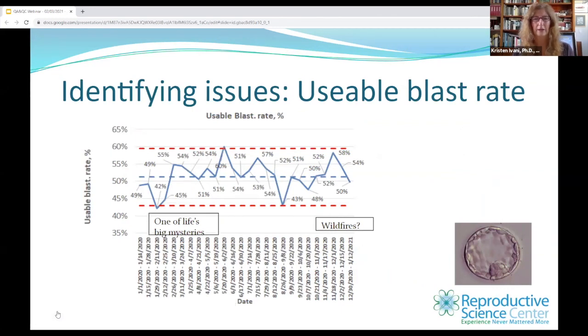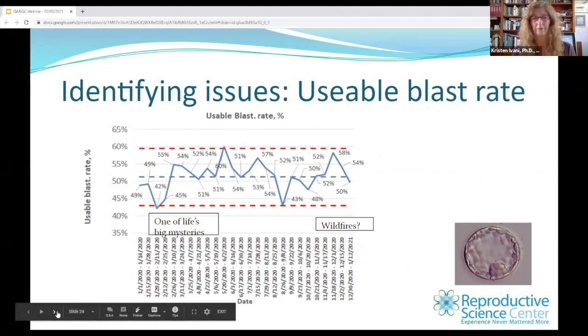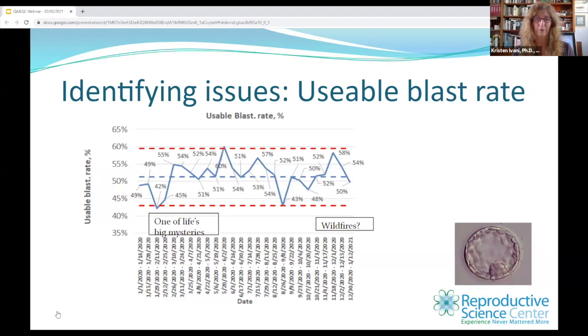This is the usable blast rate, also done every two weeks. We had a dip in late January — one of life's big mysteries, because you look and look and you can't find anything. We also had a dip in August, which we had a lot of wildfires in California. In spite of the excellent air quality system, we still had air getting into the lab and into the clinic, and that's what we're attributing that to. This should be pretty consistent, with the average right around 51 to 52%.